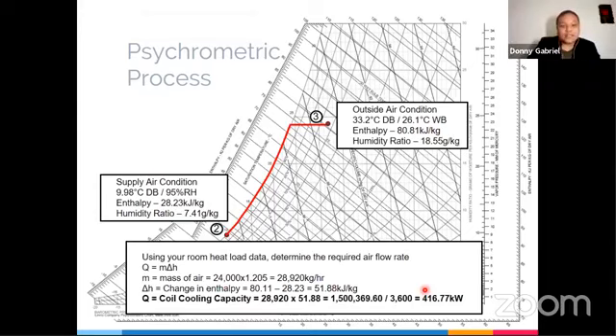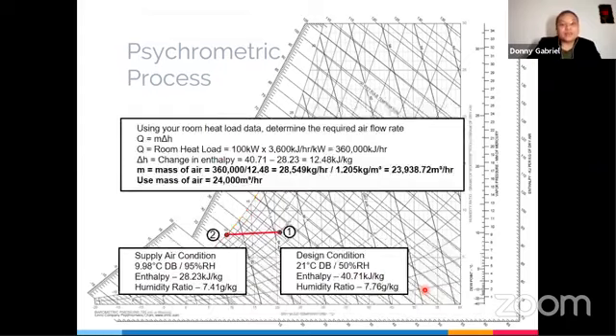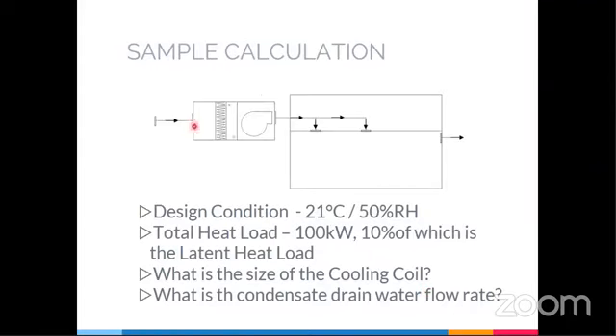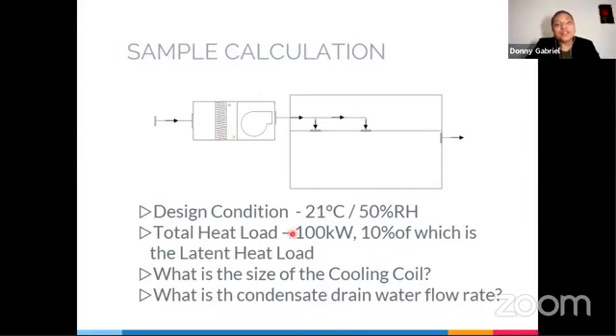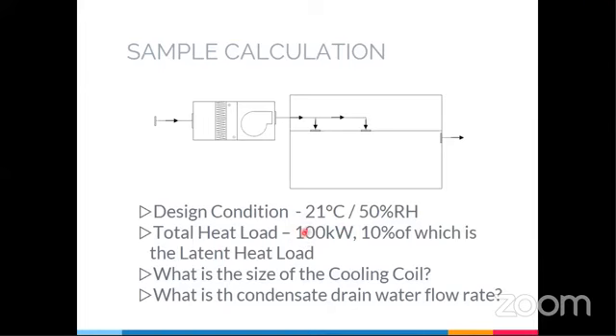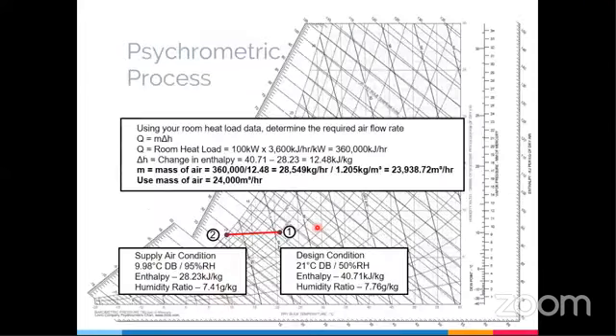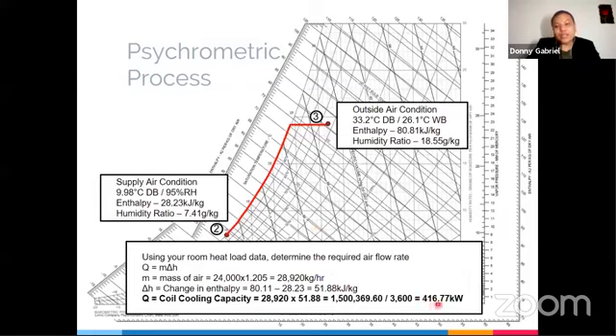Okay. So Adrian is correct. The size of the coil is not necessarily the size of your heat load. Your heat load is about 100 kilowatt, but your coil, you could see in our calculation, is about 400 kilowatt. Sir Danny. All right. Sir Danny, excuse me. Yes, sir. Kapag po, halimbawa, na-design natin, exact 100, meron ka bang recommended percentage para tumaas yung coil cooling capacity? Lakas-lakas ng konti, sir. Hindi ko marinig.